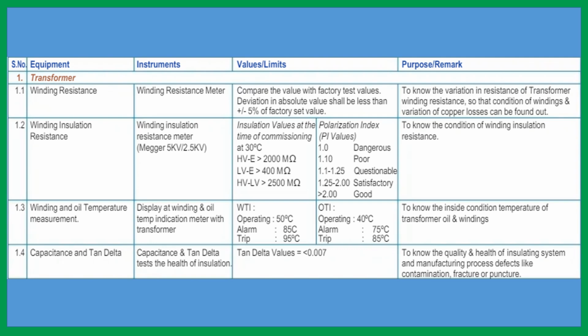This is the TSS checklist. Here, the value is given as minimum or maximum, so we have to maintain this value. If it is a minimum, you should not go below it, and if it is a maximum, you should not go above it. For example, the resistance of an individual earth electrode is 10 ohm maximum, so you have to maintain 10 or below it.